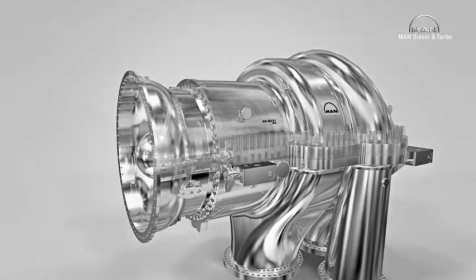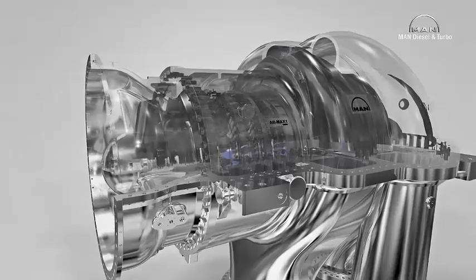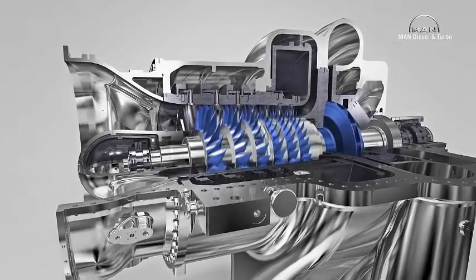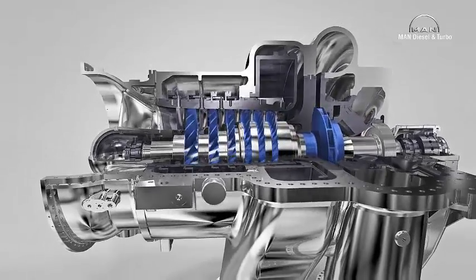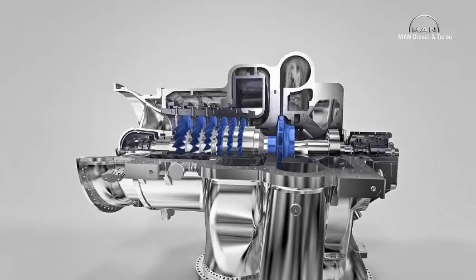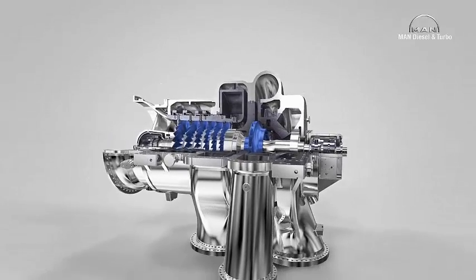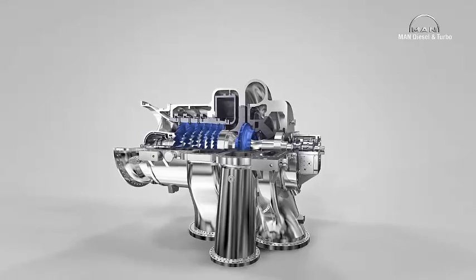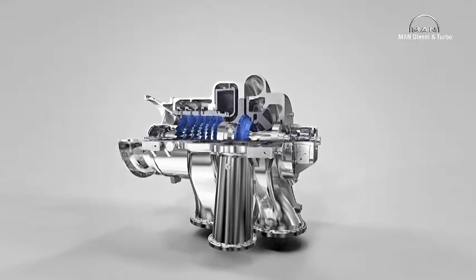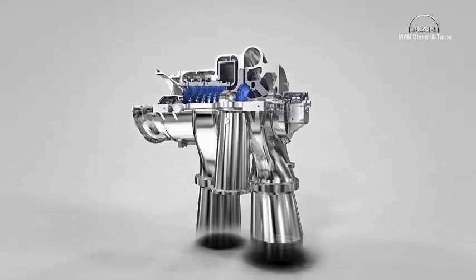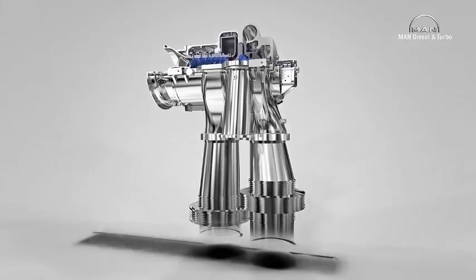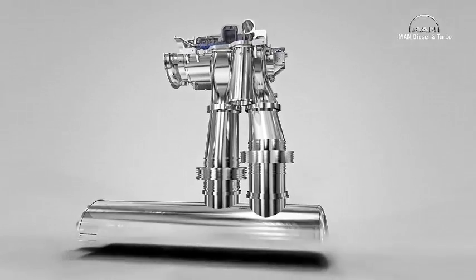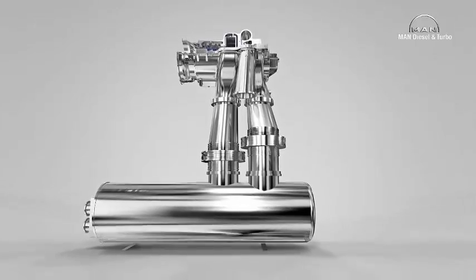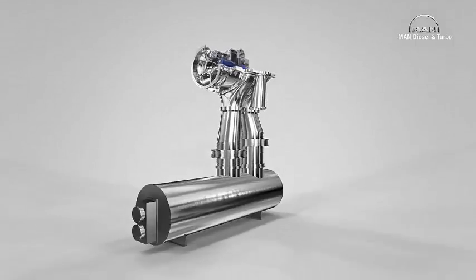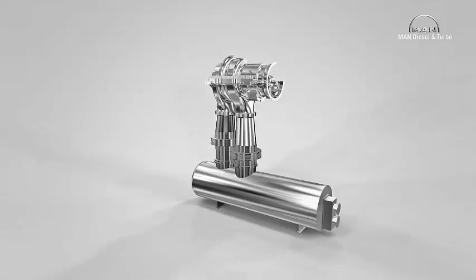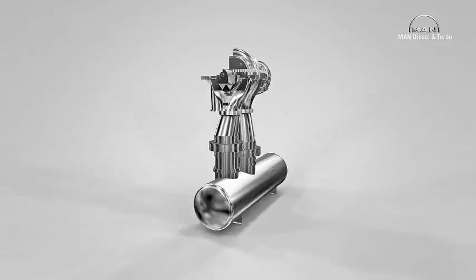The basic design of an axial flow compressor is similar to that of a fan. Blades are mounted around a shaft. In order to increase the effect, several of these blade rows are arranged axially, one behind the other. This axial stage group is often combined in a machine with one or more downstream radial stages in order to further increase the discharge pressure. A compressor of this type, such as the AR Max 1 shown here, is known as an axial radial compressor.